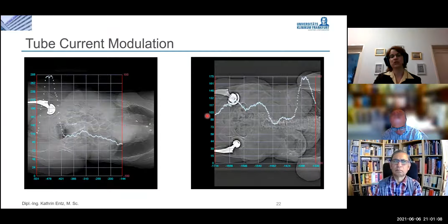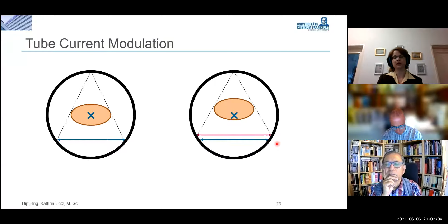Also, one point that you have to keep in mind for the tube current modulation is that you have to place your patient directly in the isocenter, like this one here. So if you take an anterior-posterior topogram image, then this would result in a patient size according to this arrow here. If you are placing the patient too high, if you are putting the patient table too high, then the patient wouldn't be in the isocenter anymore, and that leads to a magnification in the topogram image. That is the different arrow here, and you can already see that it's bigger now, and that means that the CT scanner thinks the patient is bigger, even though you are working with the same patient. I have two examples here.